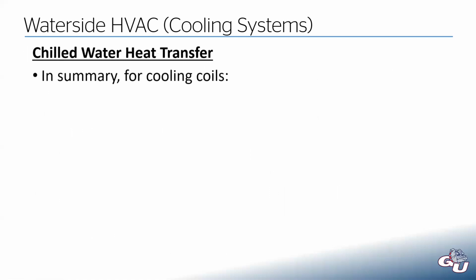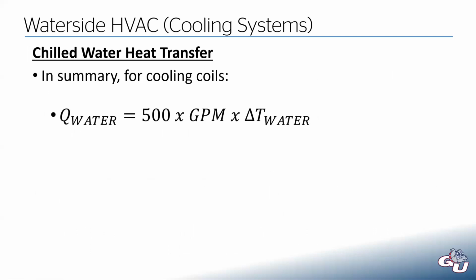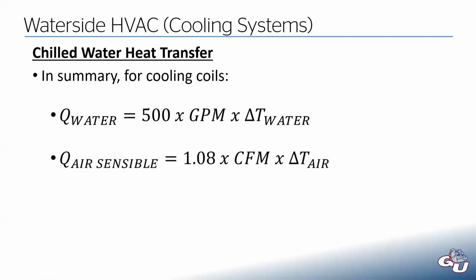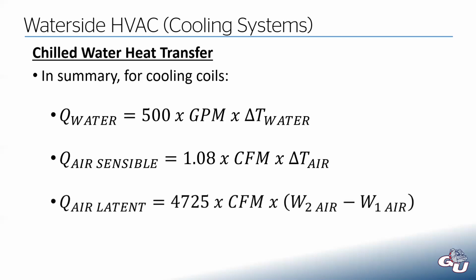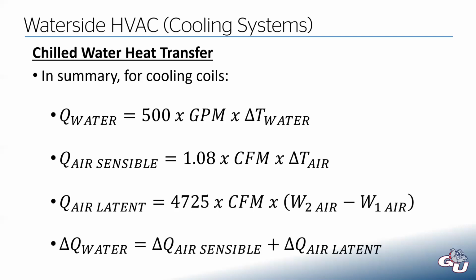In summary, on cooling coils, we have our driving equation. And as a reminder, our sensible air heat transfer equation is 1.08 times CFM times the delta T of the air. The latent load of the air would be 4,725 times CFM times the delta in the humidity of the air, in versus out. And then the delta Q on our water is going to be equal to the delta Q sensible plus the delta Q latent on the air side. So this is kind of a review of multiple previous lectures where we've talked about water side heat transfer and air side heat transfer.